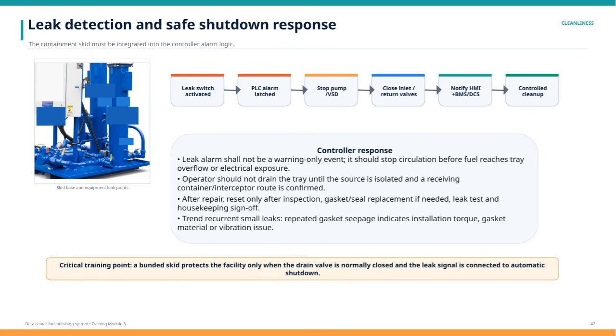After any repairs, resetting the alarm and system should only happen after thorough inspection, replacement of gaskets or seals if needed, conducting a leak test, and receiving a housekeeping sign-off. It's also important to monitor and trend small, recurrent leaks carefully. Multiple instances of gasket seepage may indicate problems like incorrect installation torque, unsuitable gasket material, or excessive vibration. One critical training point to remember is that the bund skid protects the facility effectively only when the drain valve remains normally closed and the leak signal is wired to automatically shut down the system. This ensures leaks are managed promptly and safely every time.